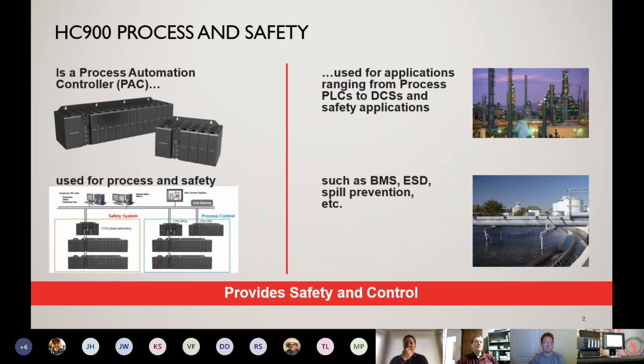The HC900, as stated in that last slide, you can use it for process or safety or a combination of both. The HC900 is SIL 2 rated for safety applications, so you can typically use this in applications such as burner management systems where you want to do the burner management in the HC900 and provide that functionality as far as startup and shutdown sequences for the burner system. You can also use it in environmental safety type applications or spill prevention. Anything that requires a higher level of safety in SIL 2 rating, the HC900 has a processor that's capable of doing that. The nice thing about the HC900 safety processor is you could also use it for process control as well.